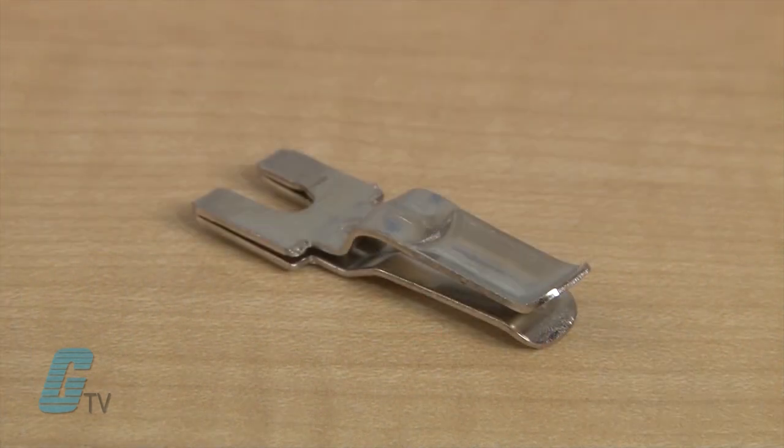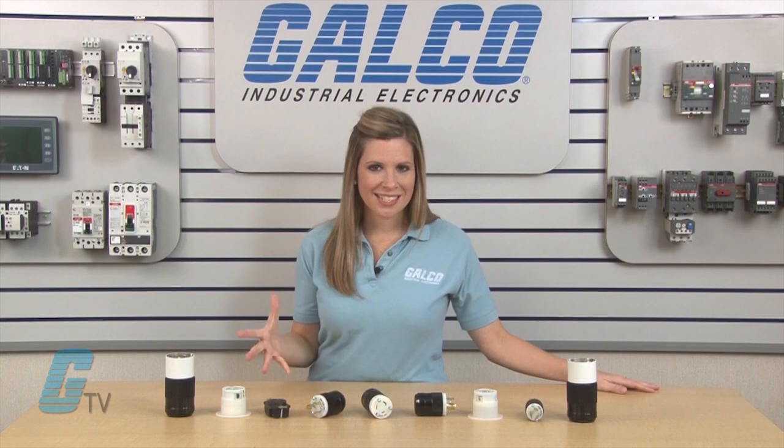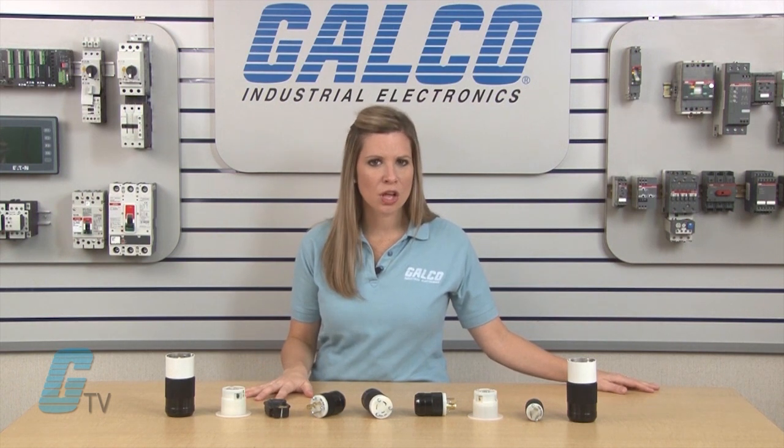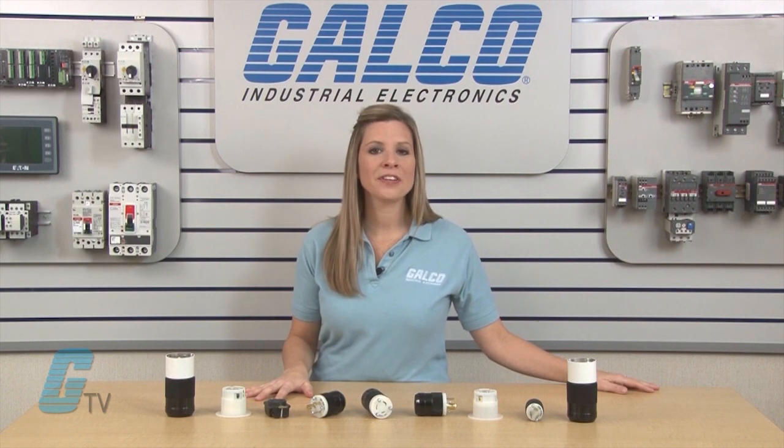Unique to the Marinco plugs are the single piece connector contacts that are a one piece design with a longer beam providing more contact pressure. This feature replaces the rivet found on other NEMA locking devices and has a lower resistance connection and can reduce the chance of heat rise.